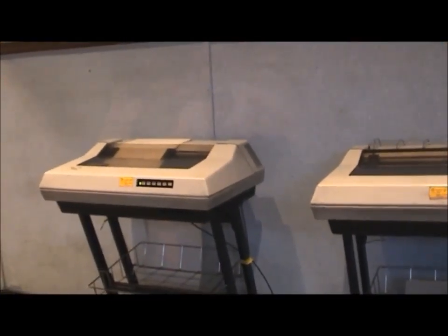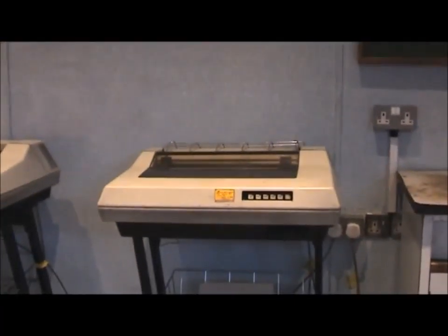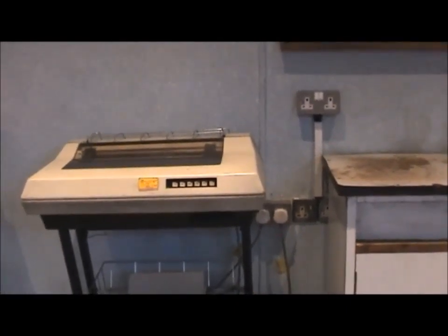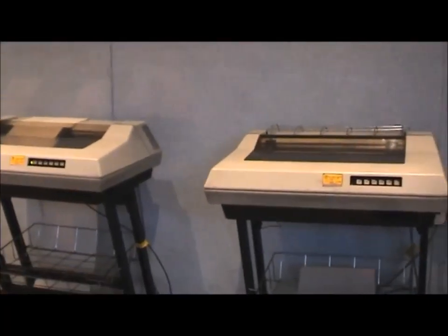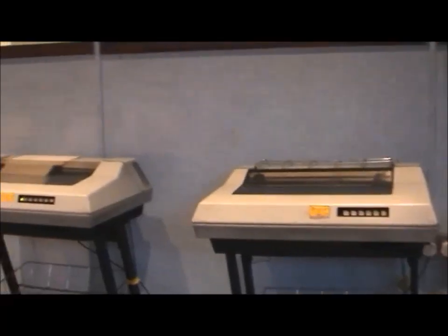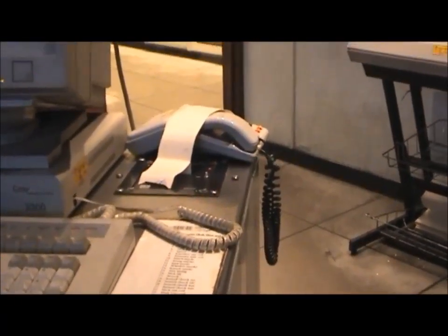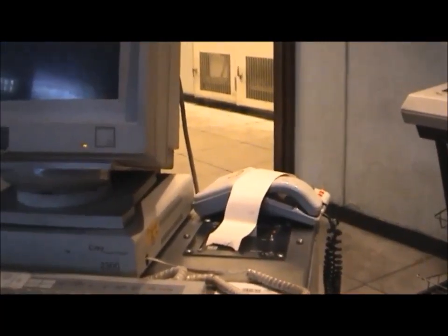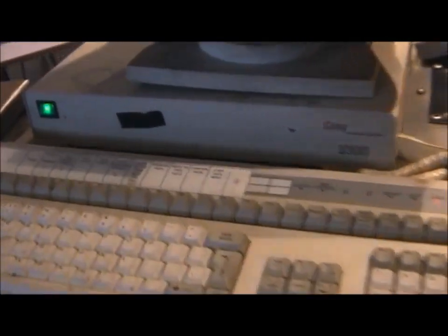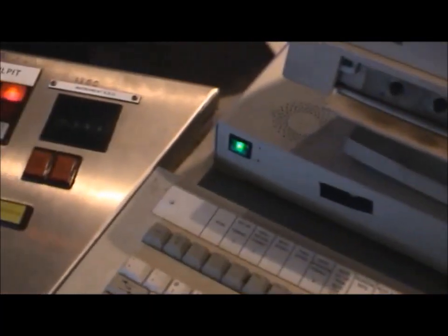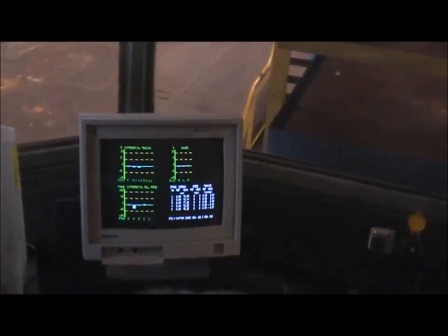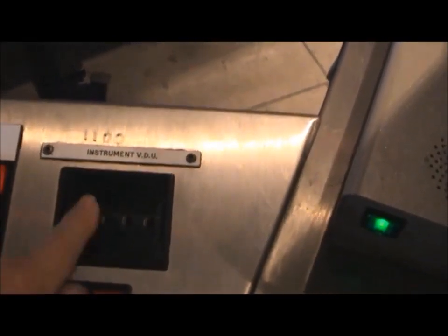That's the production logger, which needs paper in. That's the delay logger. If any logger fails, the messages are diverted to the other printer, but they should really all be in operation. If the mill stops for more than 2 minutes, a delay message will be printed and the operator prompted to enter something on the screen by the keyboard. The displays on the VDU can be altered via this thumb wheel. This will refresh, so we'll come back to the main operator's display, hopefully.